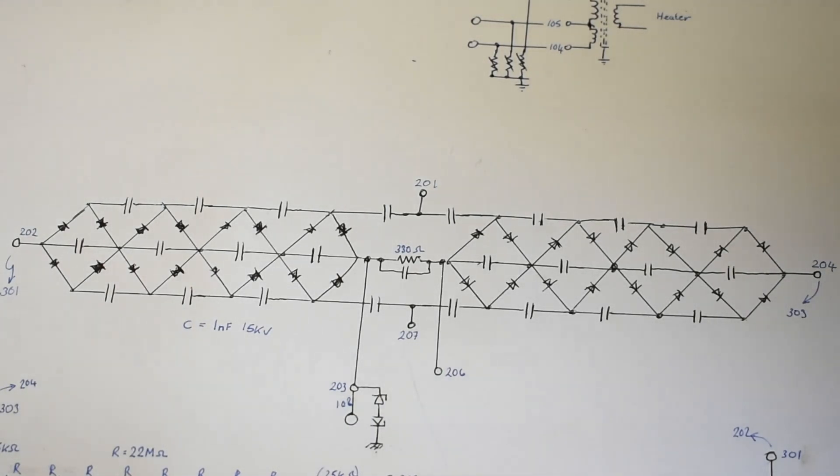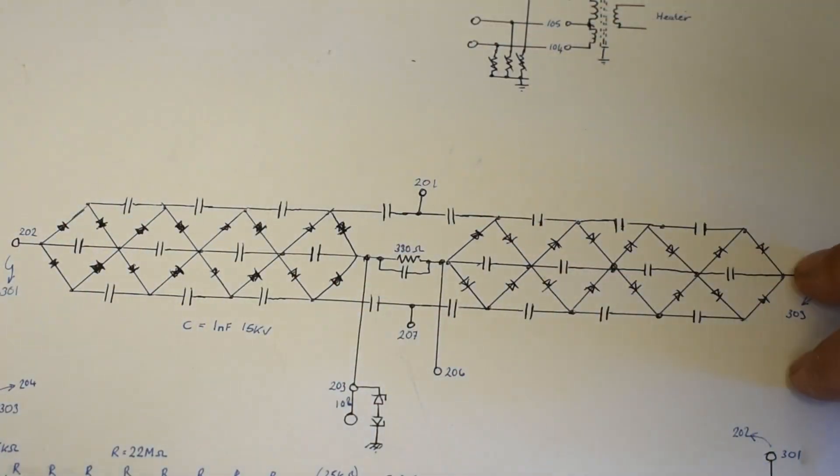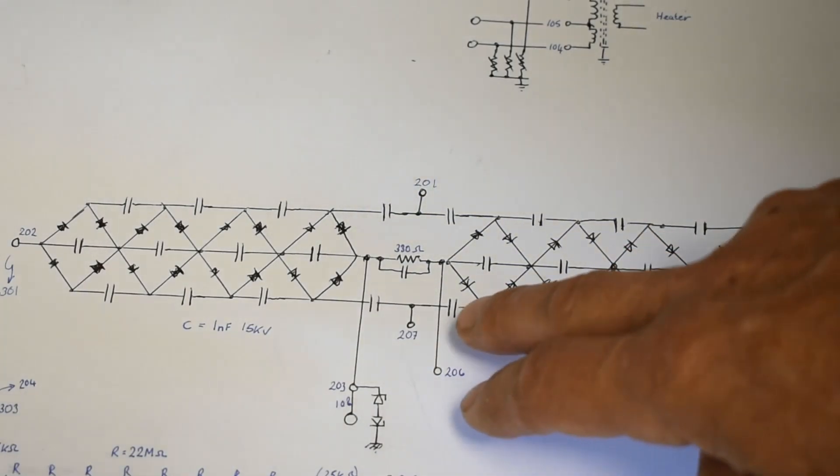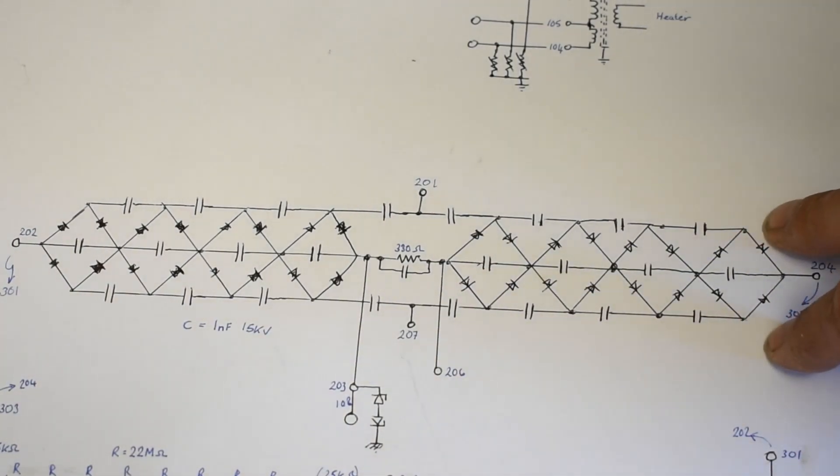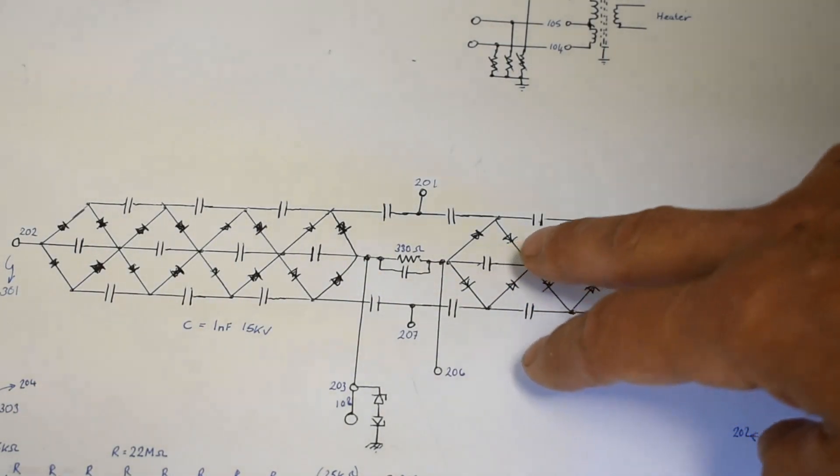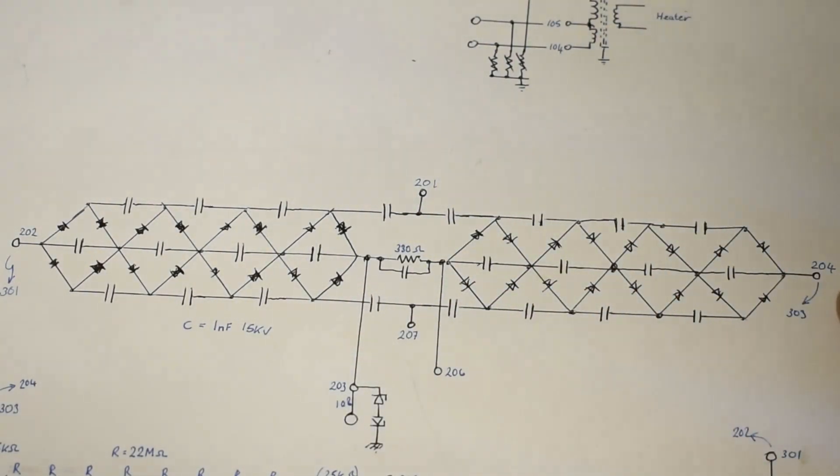It's not ideal, it's typical of X-ray units. It's a possibility that you could take this away and build a bit more onto this side, that's something I'll look at. The other nice thing about these is it's a full wave one, it's not a half wave like you find in a flyback arrangement or on televisions, that you can also disconnect it and rotate the arrangement so you would change it from a negative output to a positive output or vice versa.